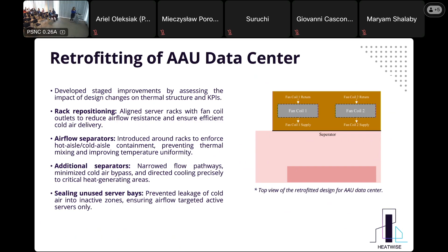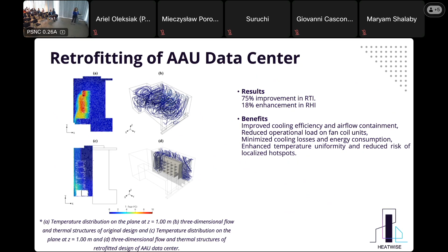Okay, so as a result, we have observed a 75% improvement in RTI and 18% enhancement in RHI. What are the benefits? We have improved cooling efficiency in airflow and airflow containment. We have reduced operational load on fan coil units, and it means that you will have lower electricity bills. Minimize cooling losses and energy consumption as well, and enhance temperature uniformity and reduce risk of localized hotspots.